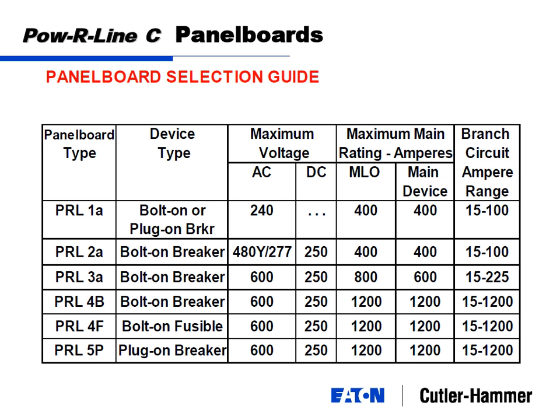And you'll even see things that are called plug-on breakers. This one here is a plug-on breaker. In reality, we don't sell plug-on breakers for panel boards. If you think about safety or longevity, and you think about a plug-on breaker where you're conducting current through something that you're plugging on, you really don't want a whole lot of amps flowing through something like that. A bolted connection is always going to be inherently safer, run cooler, be able to handle more amps.